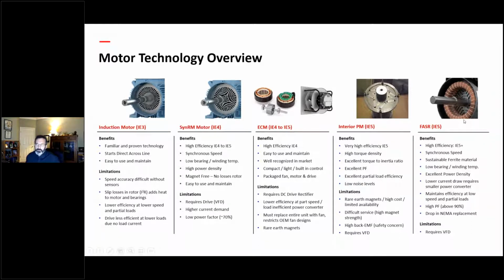But the whole point of this ferrite assisted synchronous reluctance design is to get you a product that's more typical in HVAC applications, 30 horsepower and down, and more cost effective. So the ferrites are more economical and practical at the lower horsepowers, and that's why it was incorporated into this design. Again, by adding the magnet material, it improves your power factor well above 90%. Power factor can be as high as 98% at like a 10 horsepower range.